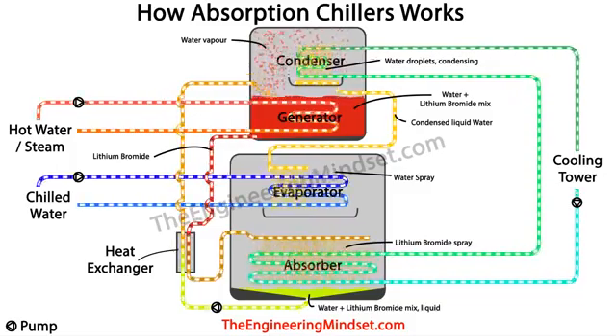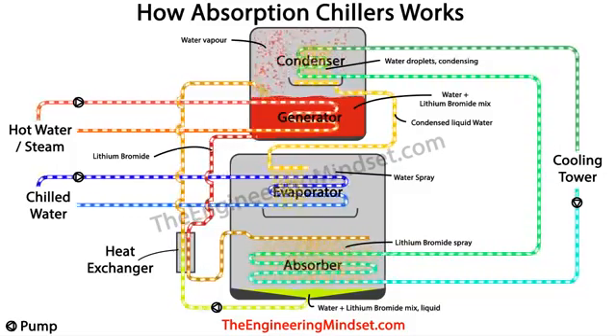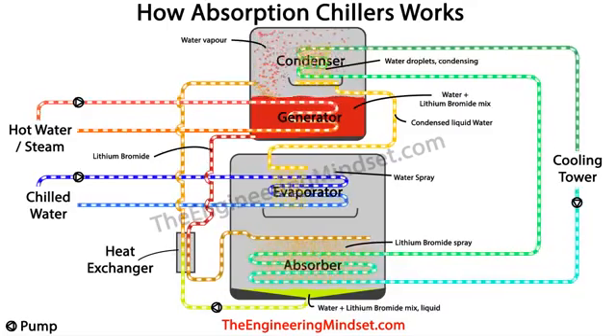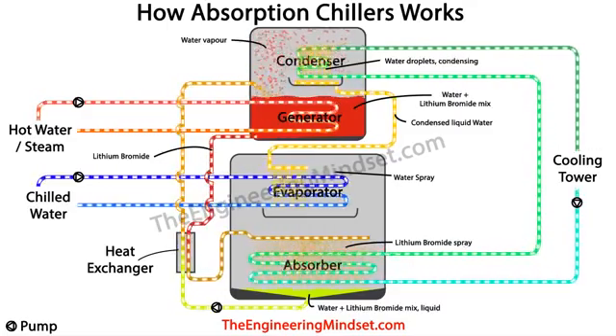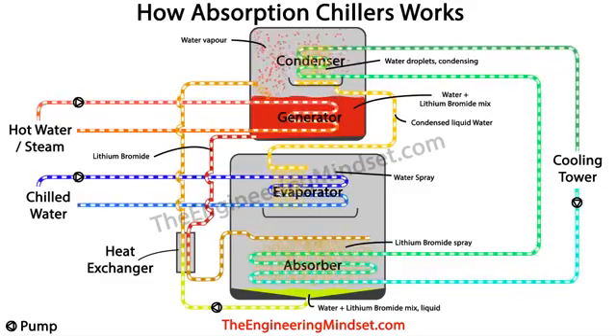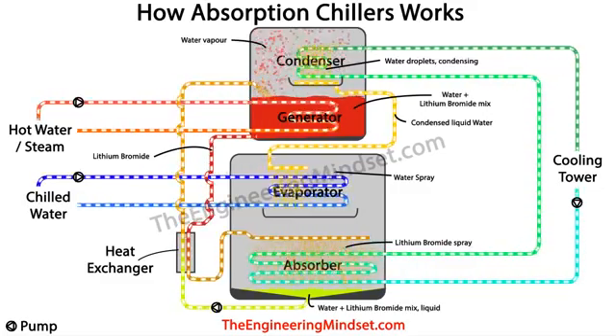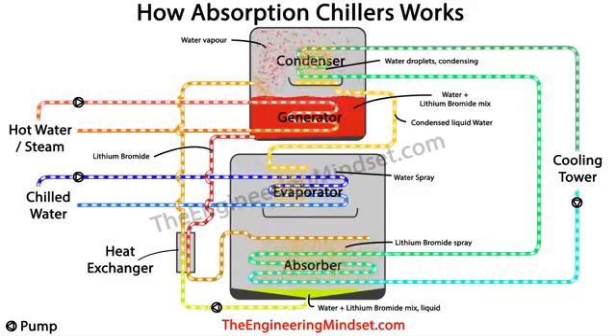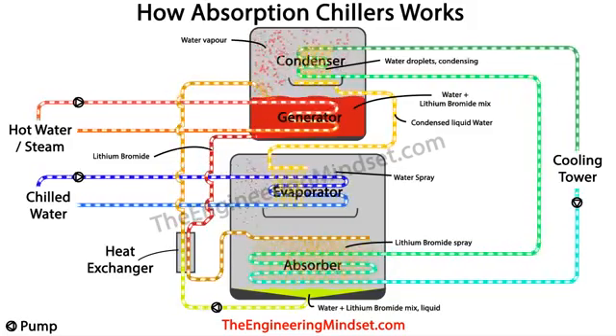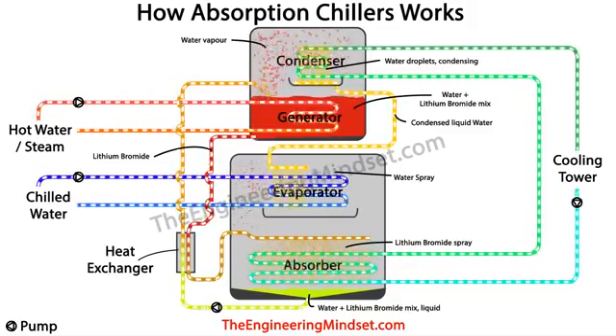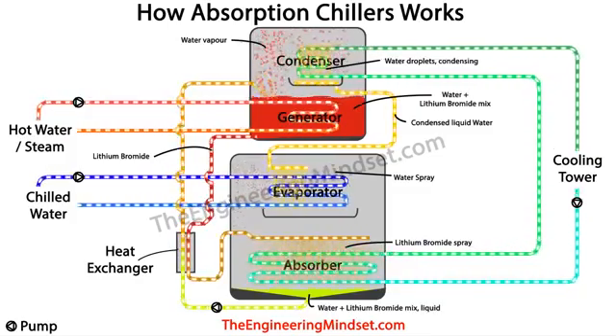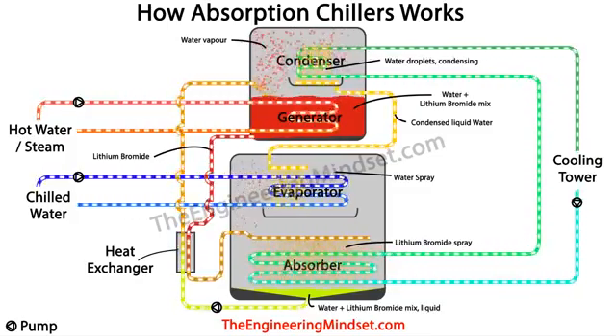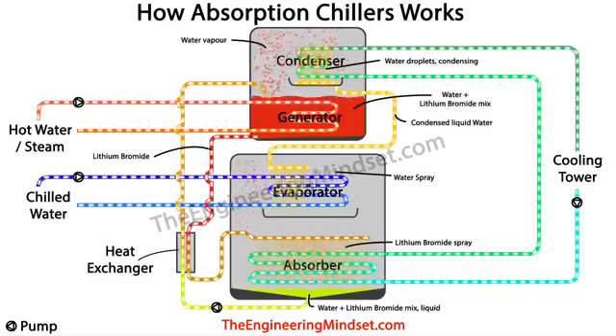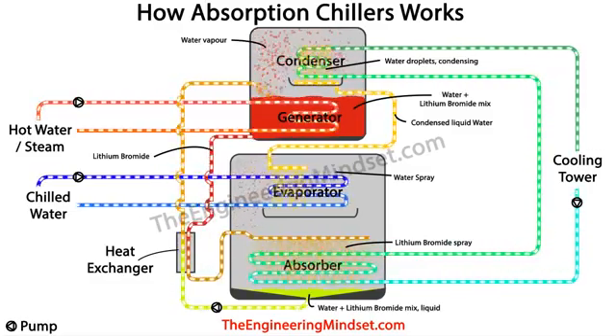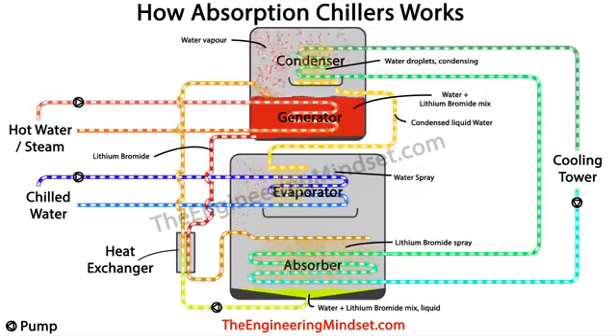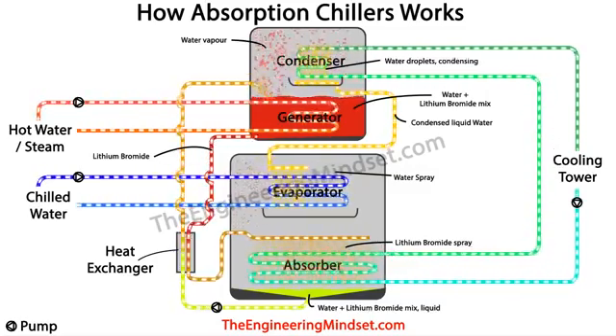A chilled water loop then runs into the evaporator, bringing all the unwanted heat from the building, which was collected from the AHUs and the fan coil units, etc. So this cold condensed water will spray over the chilled water tubes and cover the surface of the tube in a thin film of cold water. The chilled water will enter at around 12 degrees Celsius, 54 degrees Fahrenheit, and this will transfer its thermal energy, its heat, all the unwanted heat from the building. It will transfer that through the tube wall and into the low temperature water film, which was sprayed across the outside of the chilled water tubes.